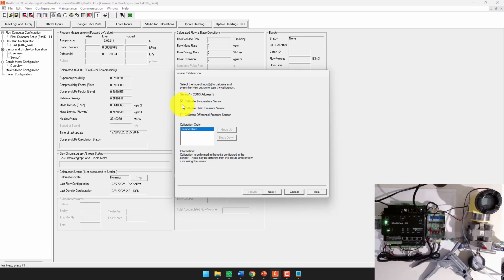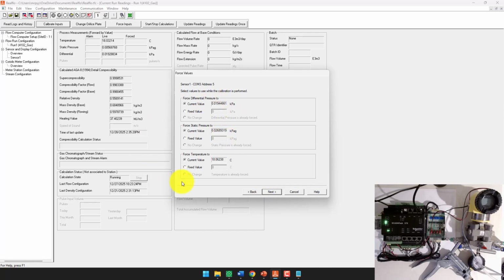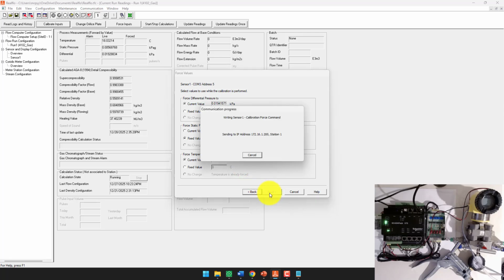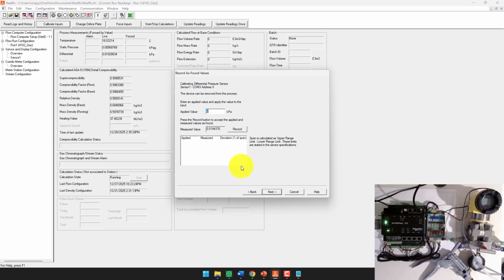Typically when you're doing this calibration, you do all three at the same time. You do temperature, static, and differential, but I've separated them. We just did static, so now we're going to do differential. And when you pick these, you can pick which ones you want to do first. But we're just doing one of them, so make it nice and easy. We'll hold the current values of this, but it's not a running site, so it's not a big deal. Sometimes if this goes into the negatives, you'll have to just force a fixed value. It won't hold a negative value in there. We'll record 0. Hit next.